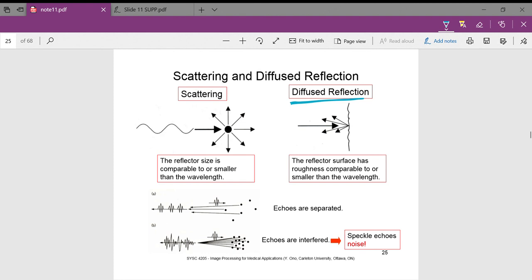Because of the numerous surfaces, sound is able to get back to the transducer in a relatively uniform manner. Scattering occurs where the reflector size is comparable to or smaller than the wavelength. Diffuse reflection occurs where the reflector surface has a roughness comparable to or smaller than the wavelength of the incident wave. Here we have an example of how speckle echoes arise: where particles are low density, echoes are separated, but where there is a high density of particles, the echoes actually interfere — this is how we get speckle noise.